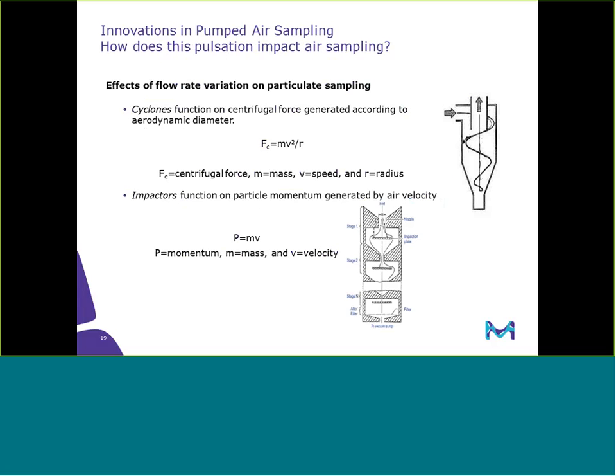There have been a number of studies, which I've listed in my reference slide, that examine the effect that pulsation can play on sampling. If we look at the basic math involved with impactor samplers, we see a term for speed and velocity, respectively. With this term closely reflecting the flow rate, pulsation maximum and minimum, so large variations, could have a definite impact, as we have seen in the reference work. However, the researchers also cited that there was a point where no significant impact on sampling efficiencies occurred with pulsations at less than 25%. So again, the ISO standard has a specification of 10%, and this would certainly alleviate a lot of that concern about particle sampling efficiencies.